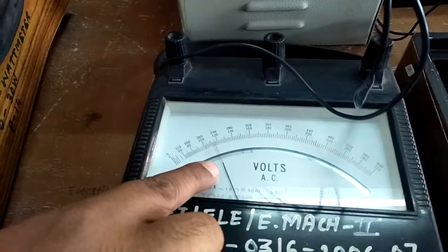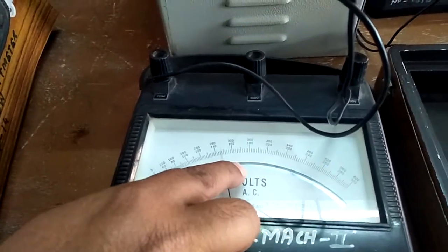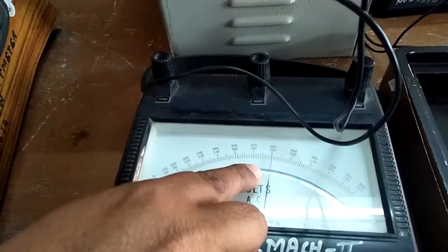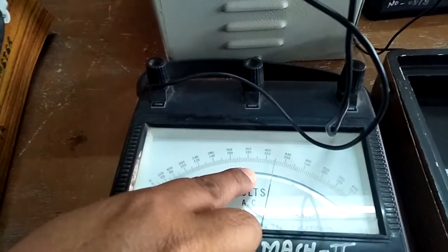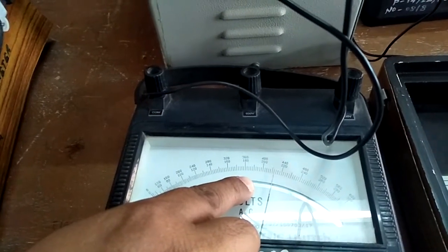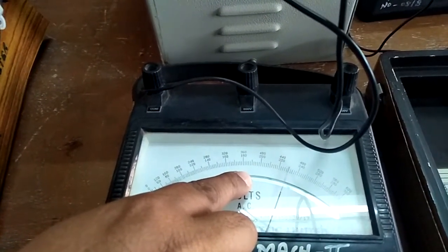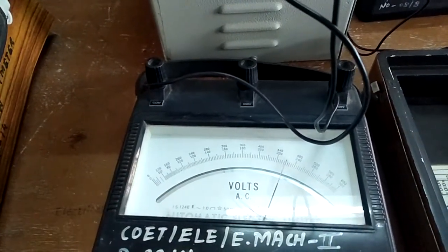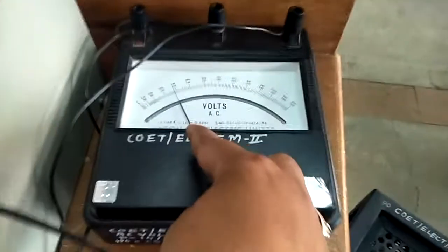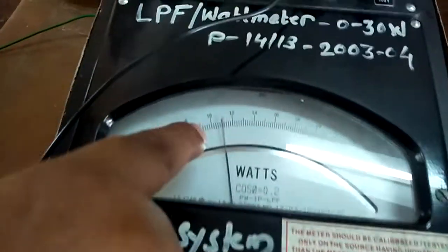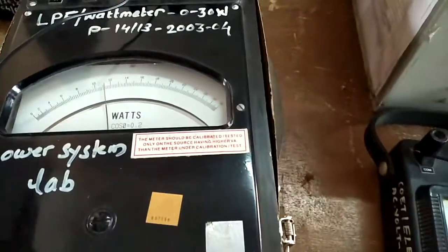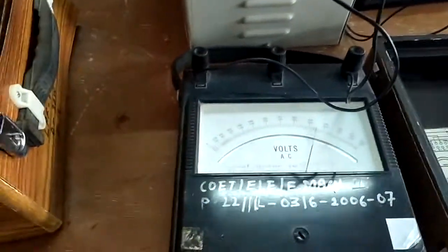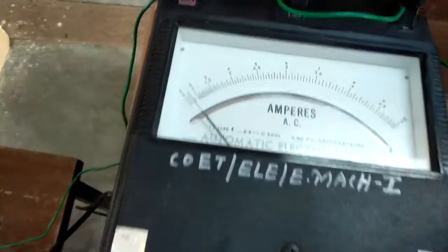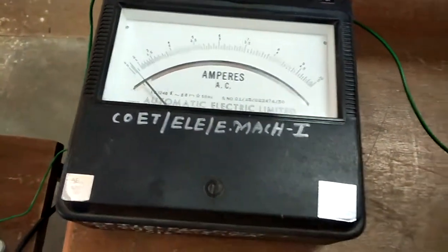So we are applying the rated voltage. You have to see how much the rated voltage is. It is a 300 range, so it is 230 volt. So rated is 230 volt. Rated voltage on the primary, and we got secondary voltage of 115 volt. Power is around 11 watt, multiplied by 4. So this is the power, and this is the no load current. So only these 3 readings are needed in this test.